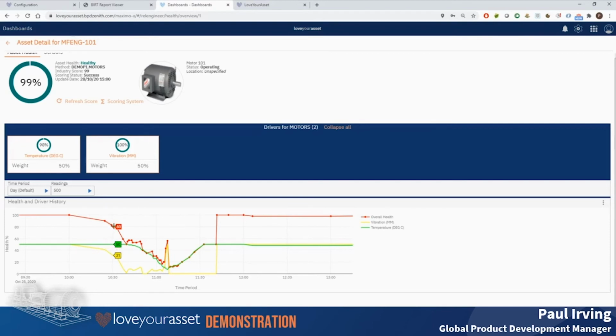And so we could do it at 80, because the temperature still hasn't started rising above 60 degrees at this point. It's still within its operating ideal, and it doesn't actually fall until the vibration is right down at 1.